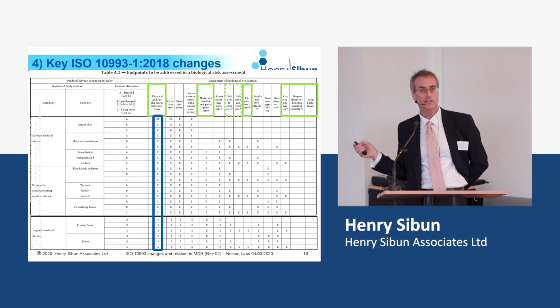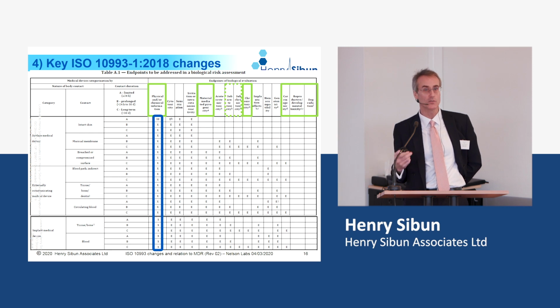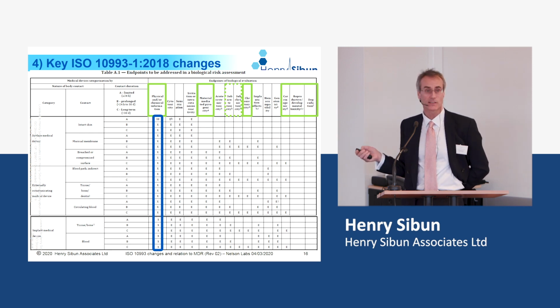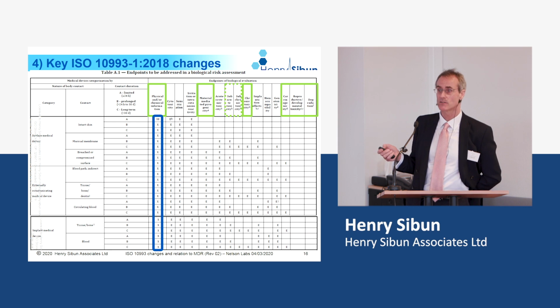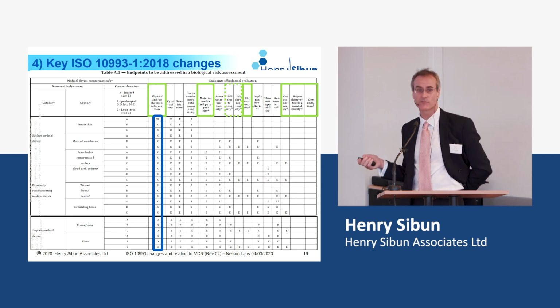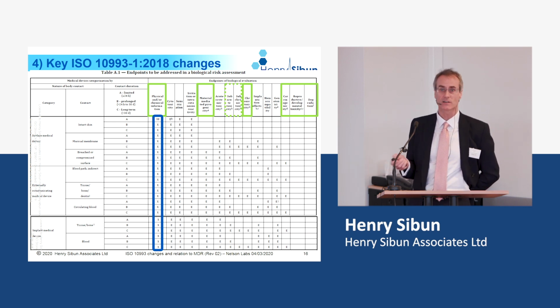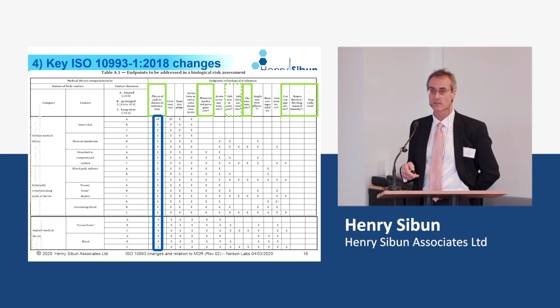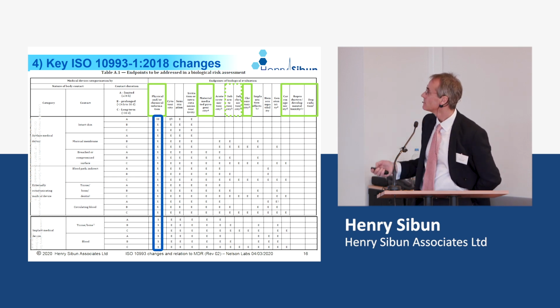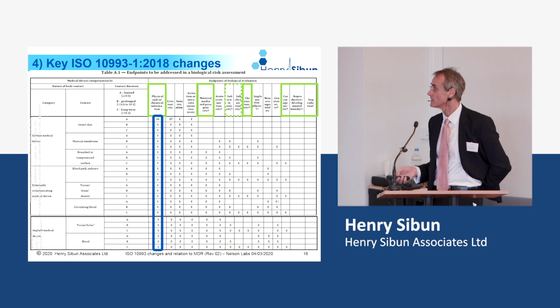You don't have to test for these, but you should be looking for data to support the safety of your device against these endpoints. That might come from testing, it might come from extractable testing, it may come from biological safety testing, it may come from the raw material manufacturer, it may come from your risk assessment, okay? But it doesn't mean you have to do all those testing.